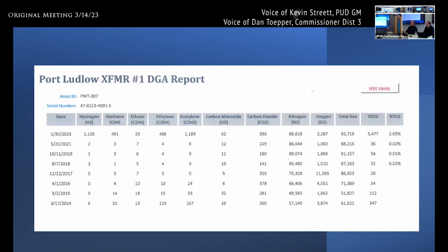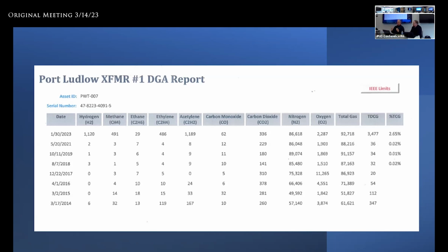So you're making them interchangeable. Not only interchangeable, but they could be run together, or they could pick up the load of the other one. If you go with that philosophy, we don't need to buy 25 MVA transformers. We're better off going with 2 20s than with the larger transformer.